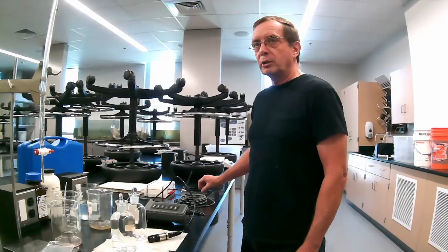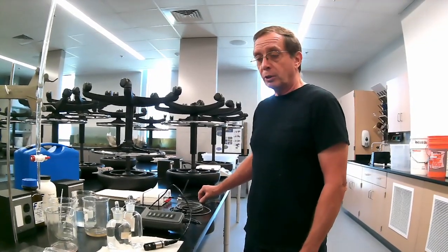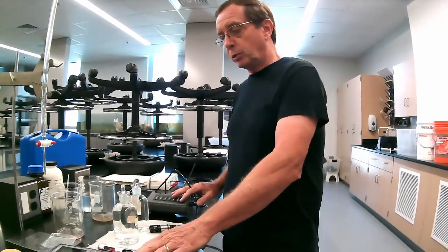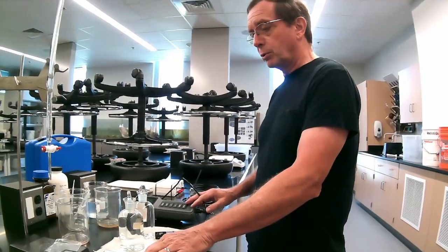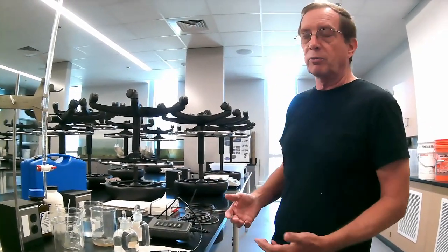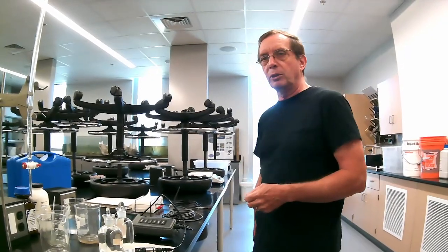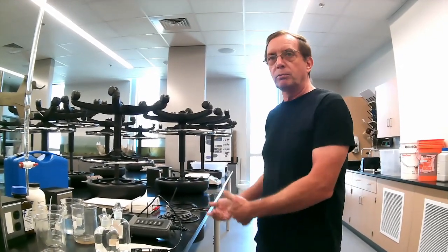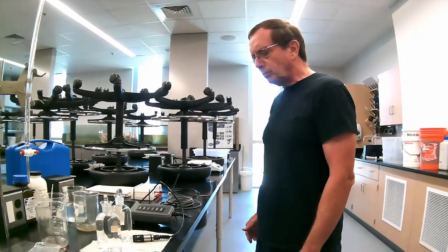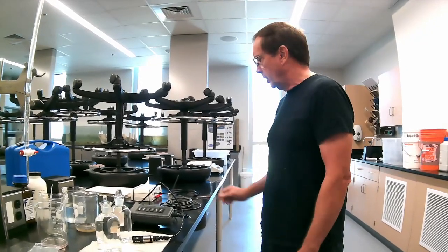They are incredibly accurate. These meters that we talked about earlier, the redshift and the Clark electrodes, have to be calibrated all the time. As a matter of fact, if you're using them in the field, they recommend that you calibrate them between measurements to keep them nice and tight.